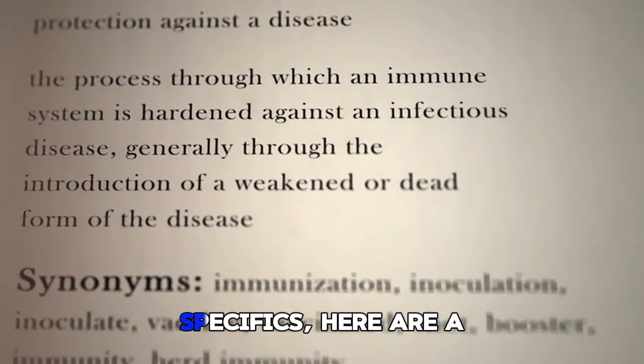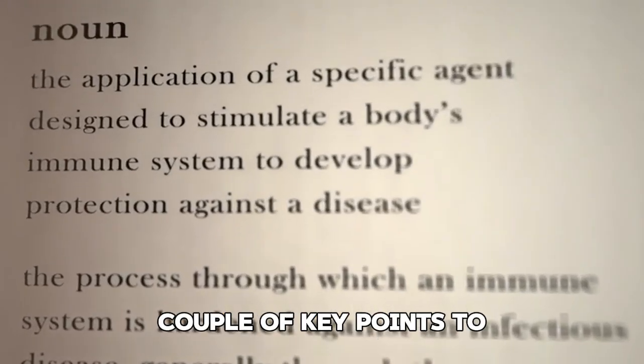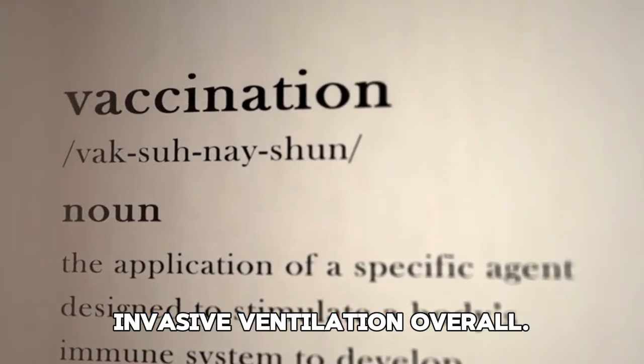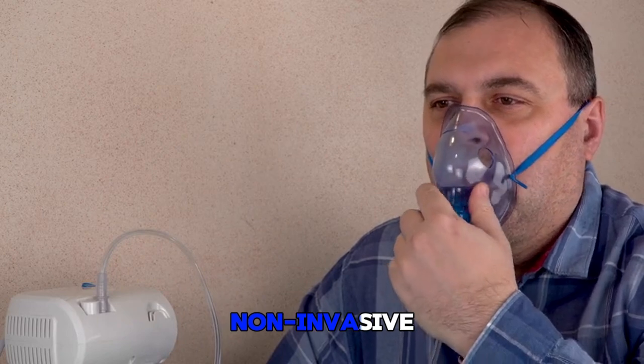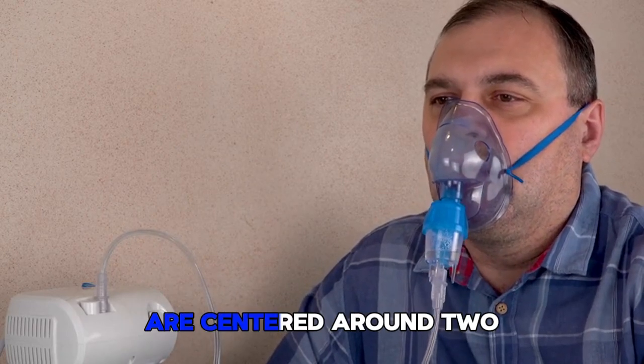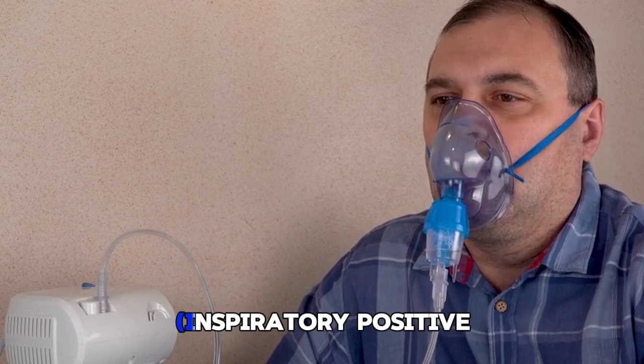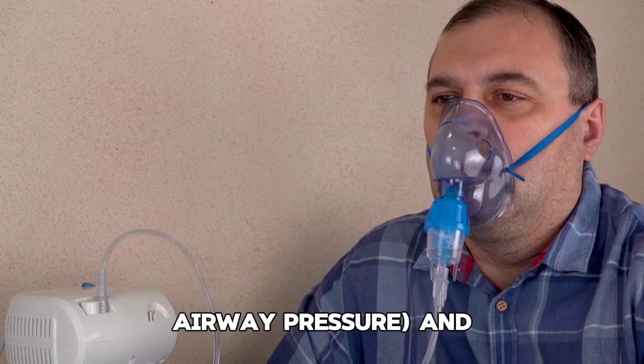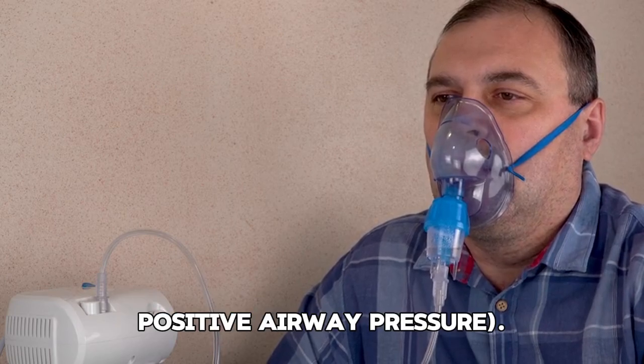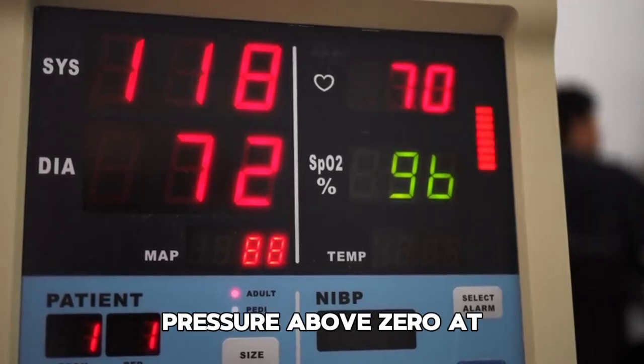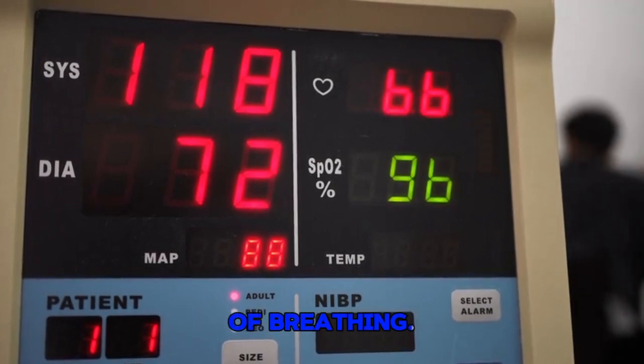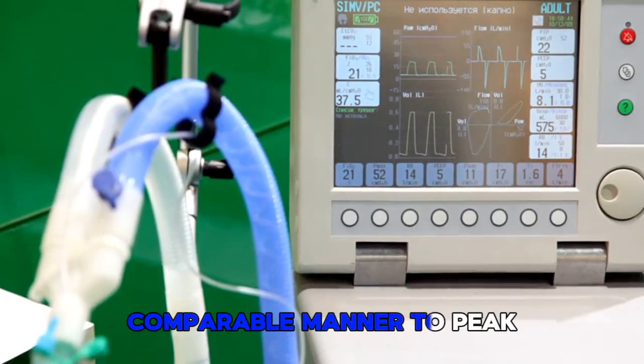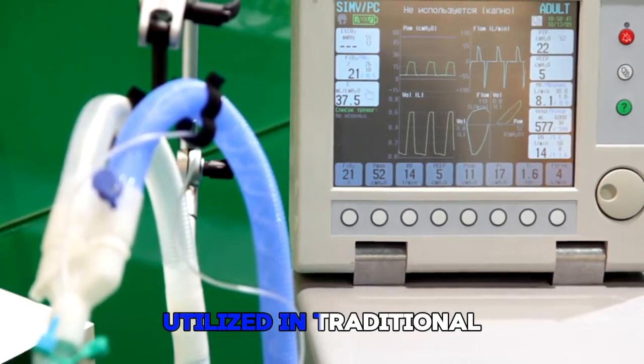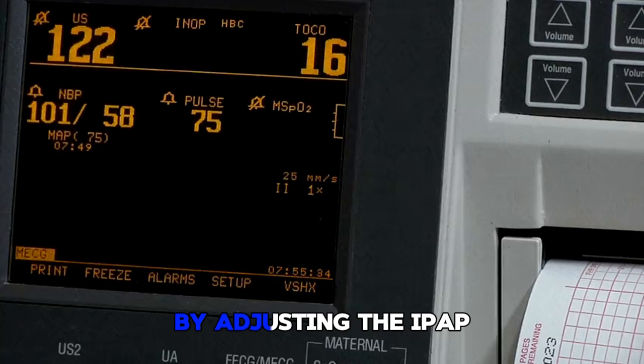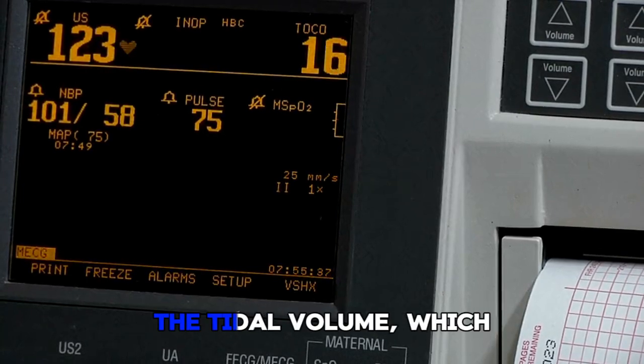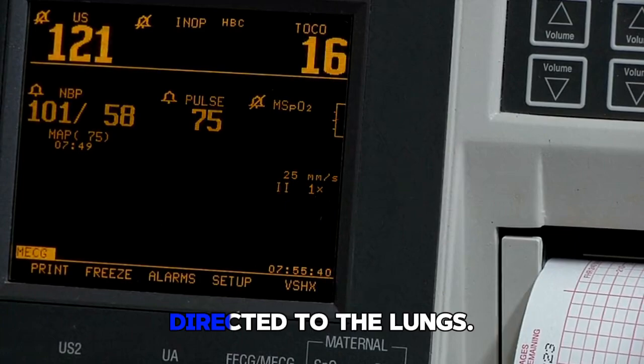Before we delve into the specifics, here are a couple of key points to understand about non-invasive ventilation overall. The fundamentals of non-invasive ventilation settings are centered around two main aspects: IPAP, inspiratory positive airway pressure, and EPAP, expiratory positive airway pressure. IPAP represents the pressure above zero at the inspiratory phase of breathing. It operates in a comparable manner to peak airway pressure utilized in traditional mechanical ventilation. By adjusting the IPAP setting, you can enhance the tidal volume, which is the air amount directed to the lungs.